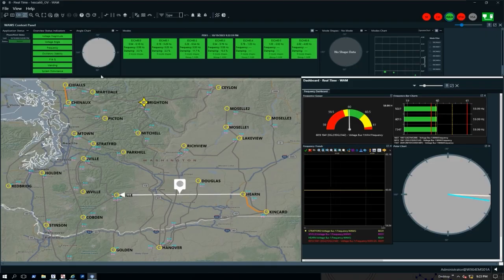What we have across the top, we're in the WAMS context. If you have PhasorPoint, some of these displays will be familiar to you, but we have our overview status indicators of WAMS. Starting at the bottom, typically anytime there's a system disturbance, we're going to see this indicator turn yellow or red, typically red. Then WAMS is looking for islanding conditions, power and megavar overloads, oscillatory stability, frequency issues, and then voltage angle and magnitude issues. We have our oscillatory mode shapes, so we have our different oscillatory mode groups, starting from 0.04 going all the way up to 4 Hertz in this example. We've got mode shape data to the right.